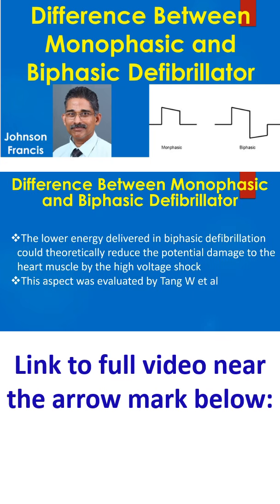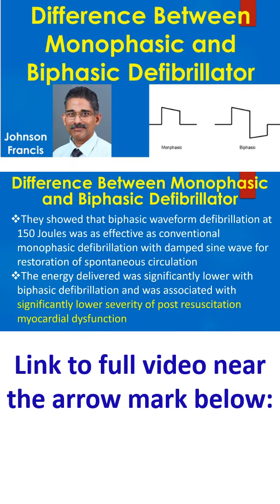The lower energy delivered in biphasic defibrillation could theoretically reduce the potential damage to the heart muscle by the high voltage shock. This aspect was evaluated by Tang and Associates.